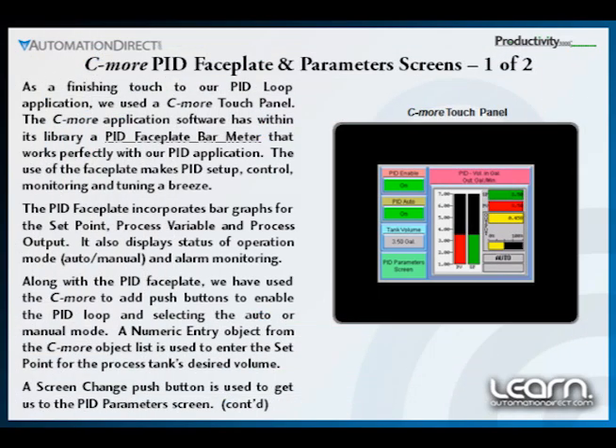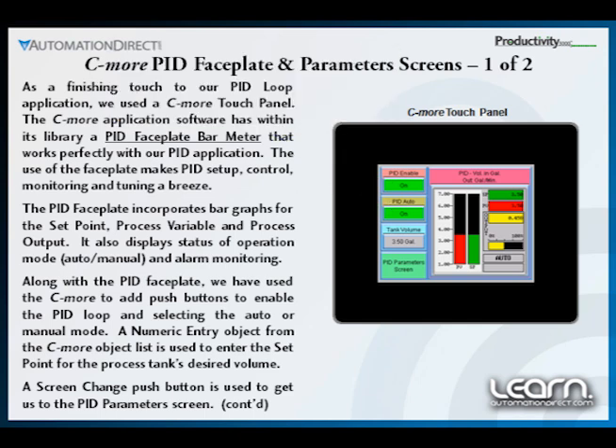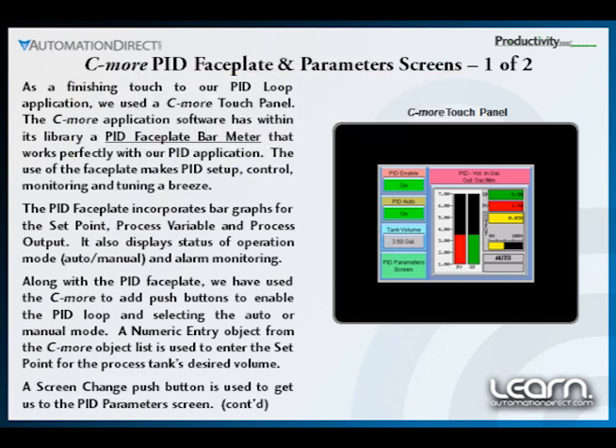As seen here, I added additional push buttons to enable the PID loop control and the ability to select auto or manual operation. I also created a numeric entry to allow the operator to enter the set point value, and a screen change button to allow access to our PID parameter screen. I'll explain more on this in a second.